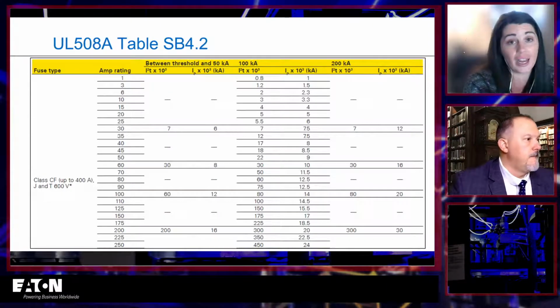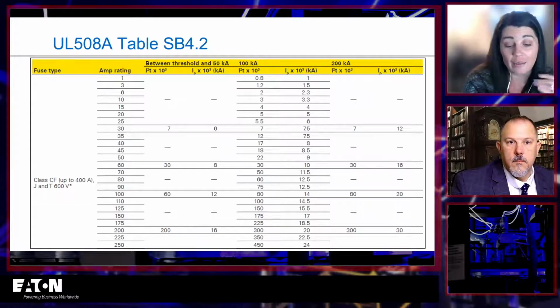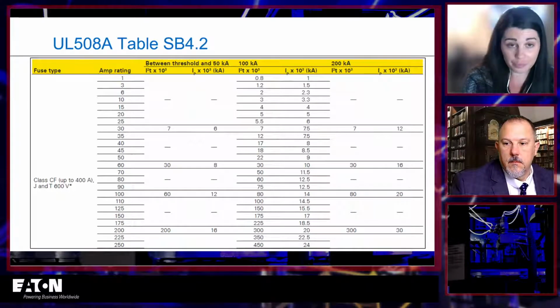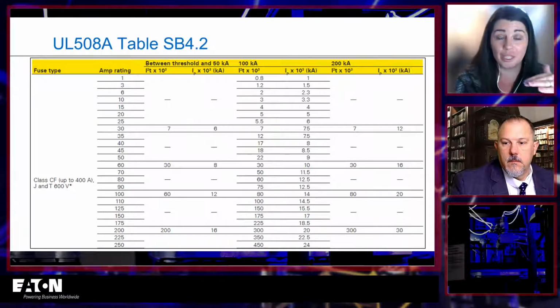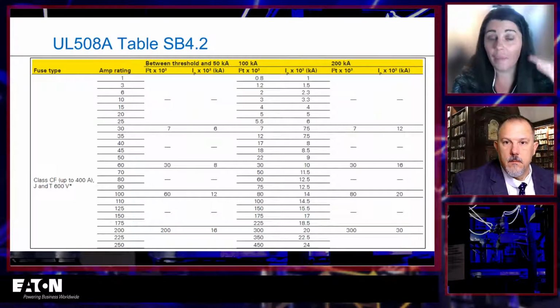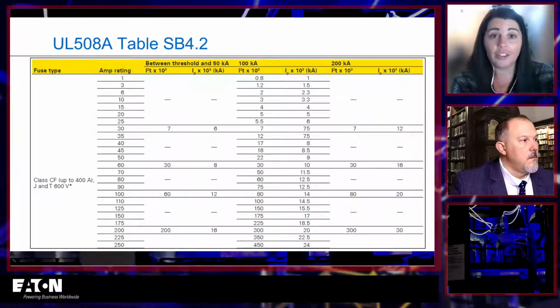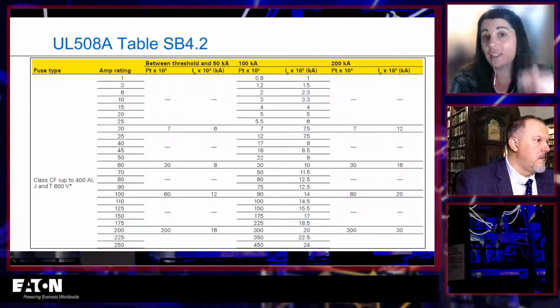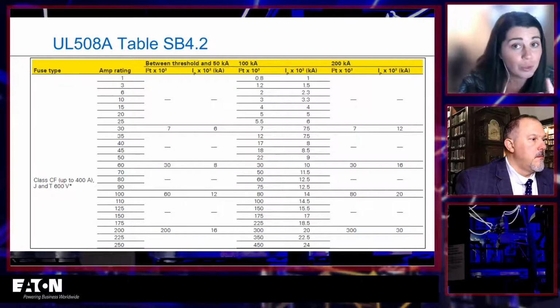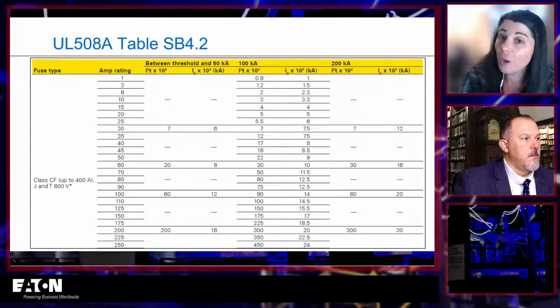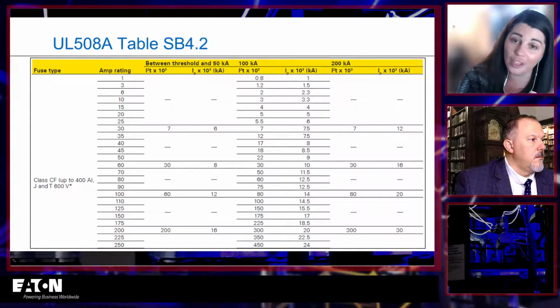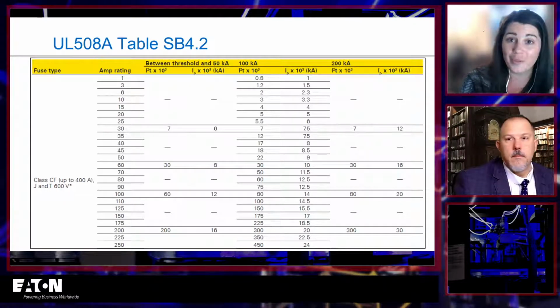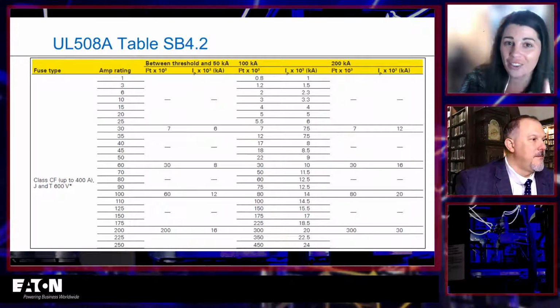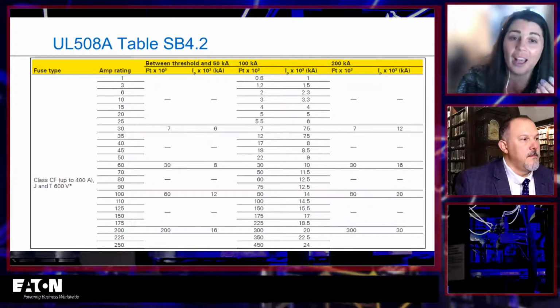These are the maximum let-through that any fuse can let through during a fault by UL standards, right? So if it's going to be a Class J fuse, by definition, a 100 amp version of this, when it sees 50,000 amps, cannot let through more than 12,000 amps. Now, the actual fuse that you're using might be lower than that, and it would be great if we could use that value, but we don't. We can only use the values that are in this specific table as a result.